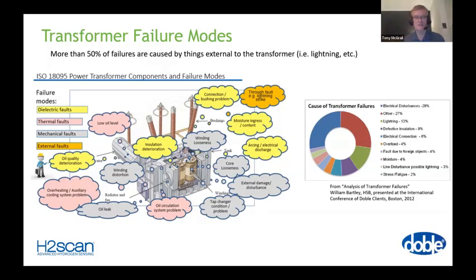There's dielectric faults, where the insulation can no longer take the voltage. There are thermal faults, where the system can no longer take the current and dissipate the associated heat. Mechanical faults, quite often due to lots of inrush current when we weren't expecting that, lots of through faults, which shake things up inside the transformer, loosen things, which make it a lot more difficult for the transformer to survive further mechanical input. And then things from external causes, lightning and so on.